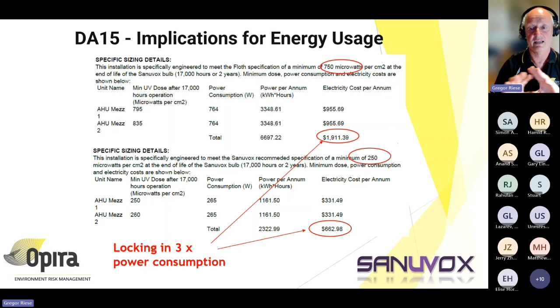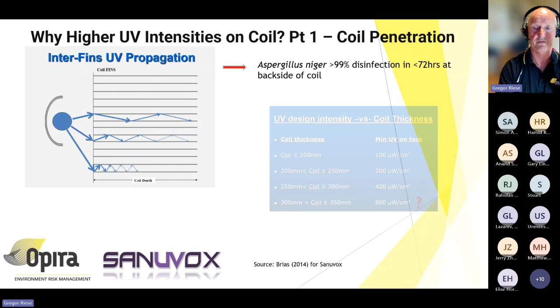But when we're doing a tender, we'll always give an alternative and we'll argue that the lower consumption will keep your coils clean, and we'll guarantee that. There might be some reasons why a company might suggest higher intensities. One of them is that if you've got a really thick coil, and some hospital coils can be over 300 millimeters thick, there can be 10-layer coils, and you need higher power to get through the coil. Our approach is that if it gets bigger than 350 millimeters in thickness, we just do both sides of the coil to guarantee that we keep that coil clean.